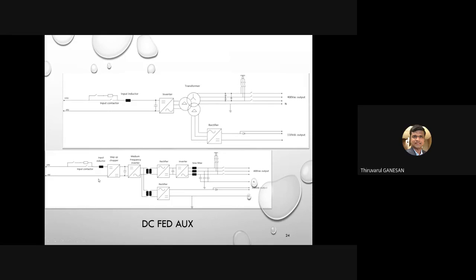Architecture 2 is quite a robust architecture, I can say, where you can see multiple conversion is happening. The input contactor, this is DC precharge contactor, main contactor, input inductor, and step-up chopper, medium frequency converter. Here you can see the rectifier. After it will go to the battery. Then the rectifier and inverter, then sinus filter, it will go to the main auxiliary loads.